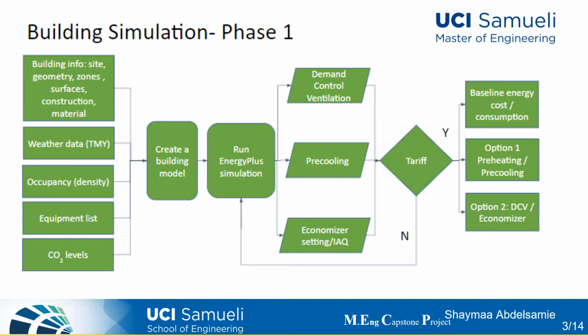We have broken our solution into two phases. Phase 1 is creating a building model using building information such as geometry, materials, weather data, occupancy, and CO2 levels. We used Energy Plus, a building simulation software, to simulate the building energy consumption baseline. We then applied different ECM strategies such as pre-cooling, demand control ventilation, and economizer operation. We ran Energy Plus to obtain the potential savings on energy consumption. We then assumed a tariff structure based on SoCal Edison rates to determine prospect savings.